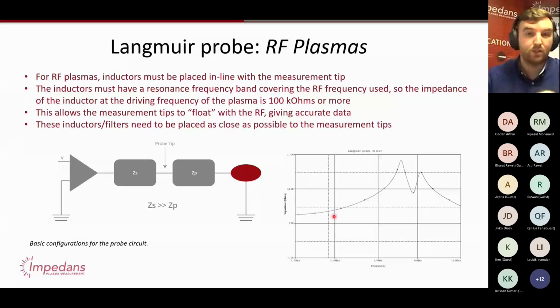There's one extra consideration when you have a radio frequency driven plasma. Essentially, because of the radio frequency, with this varying voltage versus time, we have to contend with that sort of voltage change happening over time. So the way that you make sure that your data is good is that you introduce inductors which have a resonant frequency around the driving frequency of the plasma. In other words, if you're driving a plasma at 13.56 megahertz, you have an inductor in line with that measurement, the central pin where you're doing the measurement, which has a very high impedance to ground. By high impedance, I mean on the order of at least 100 kilo ohms up to a mega ohm is a good range.